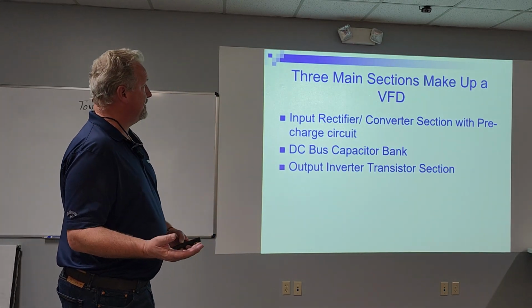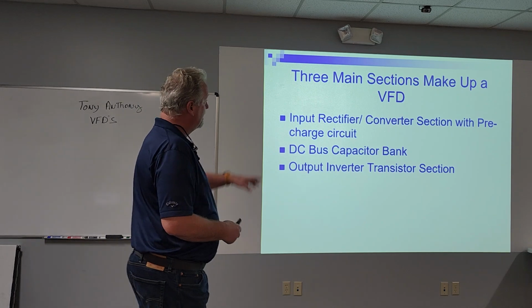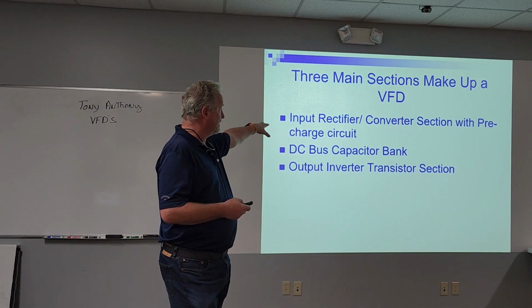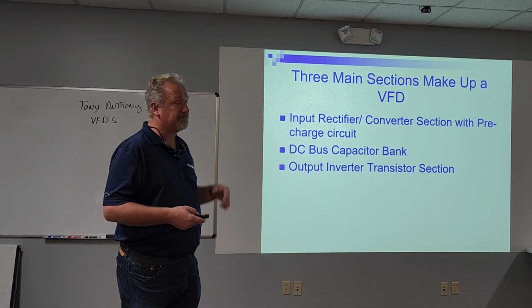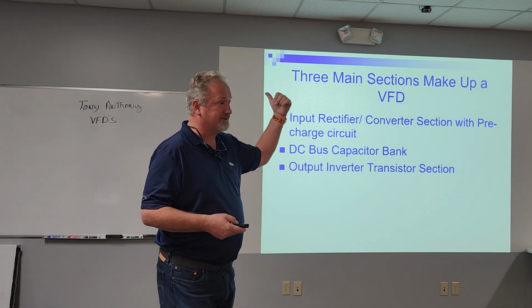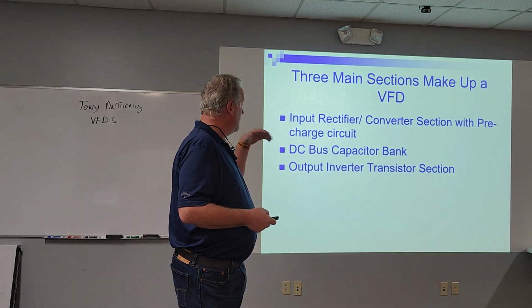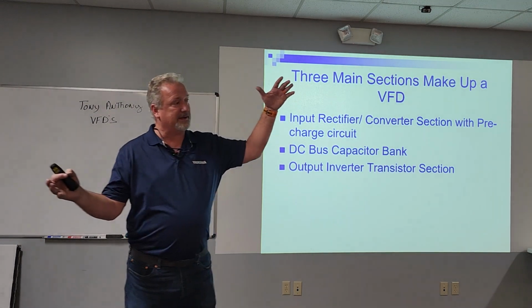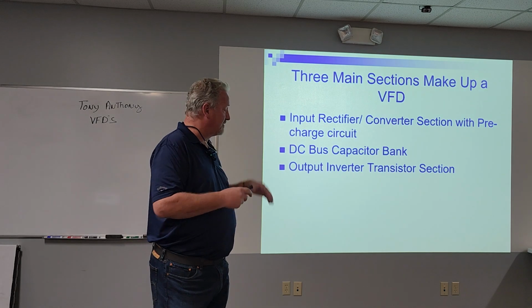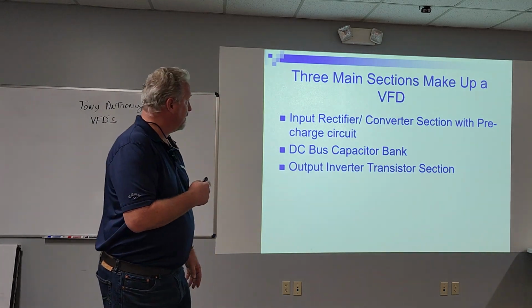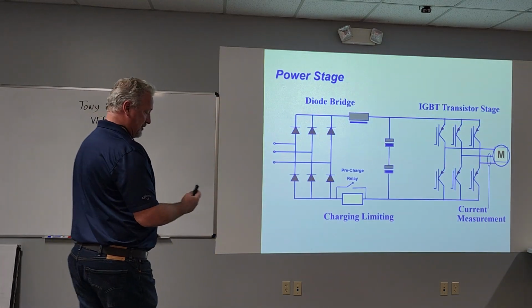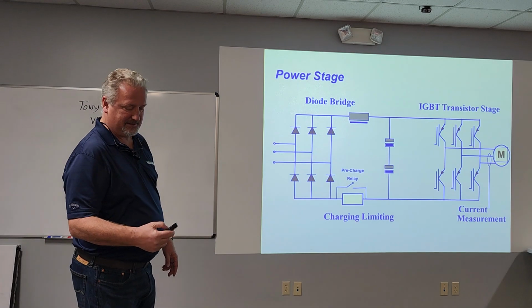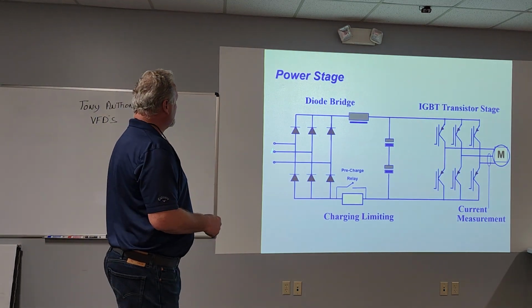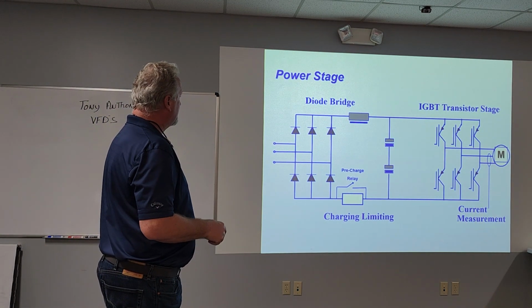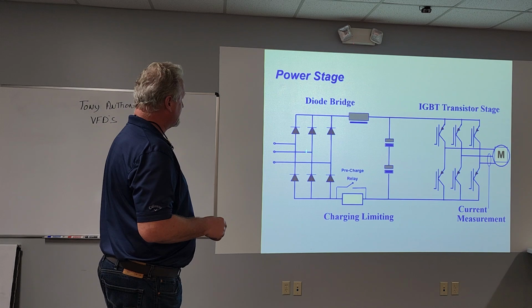Now, the drive itself. There are three main sections that make up a VFD. There's the input rectifier section, the converter section with the pre-charge circuit. That's what causes all our harmonic issues. That's also what we need. There's a DC bus capacitor bank. And then there's the output section. So on the input side, this is the diode bridge. This is what's taking AC and making DC.